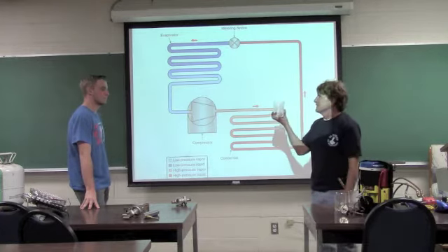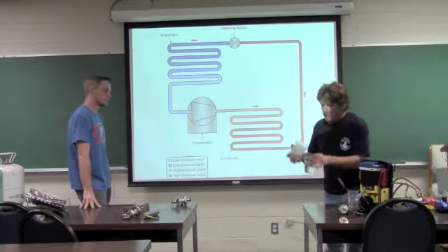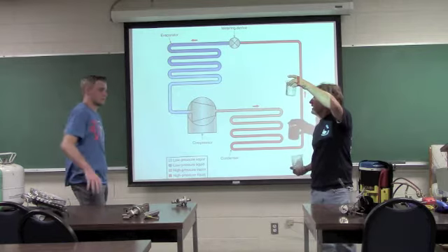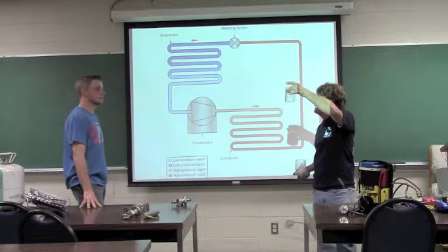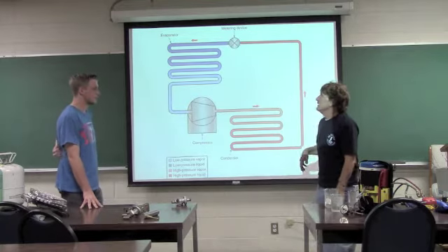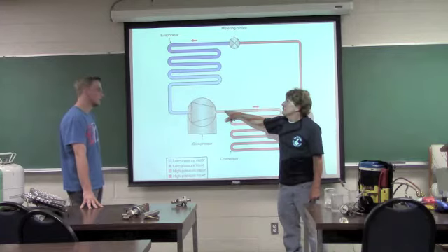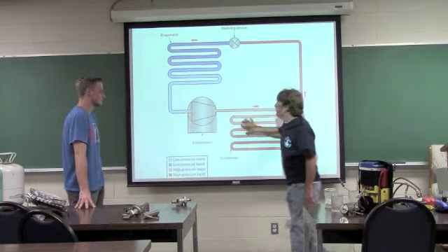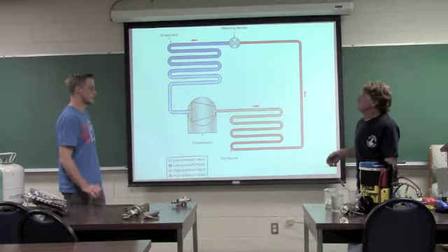If I have all ice, is this saturated? No, because it's all ice. However, if I have ice and water, and I cool it down any more, it all becomes solid ice. If I warm it up any more, it all becomes liquid. In this case, I'm dealing not with liquids and solids, but gas and liquid. Can I measure the pressure and convert it to temperature here? Nope. How about here? Nope. Only where it's both saturated. No subcooling, no superheating. Only saturation is where you can measure.